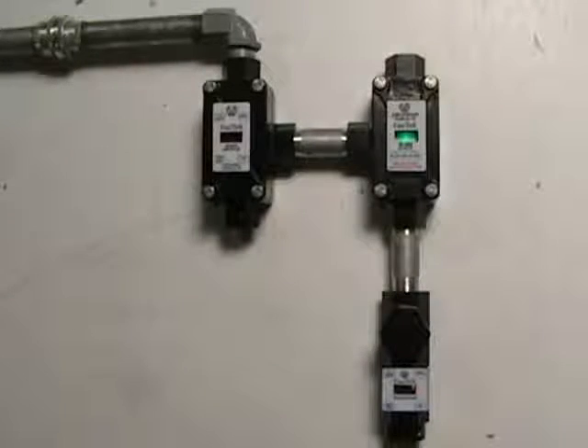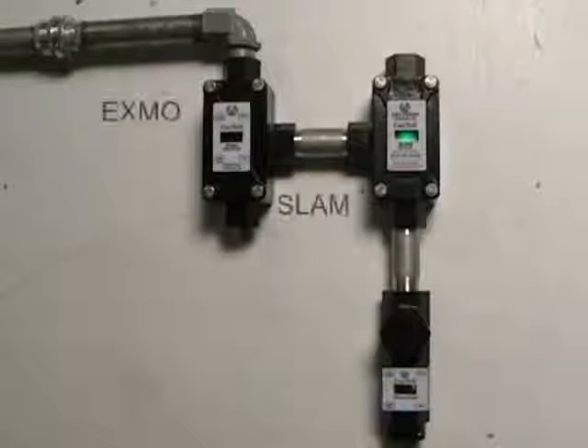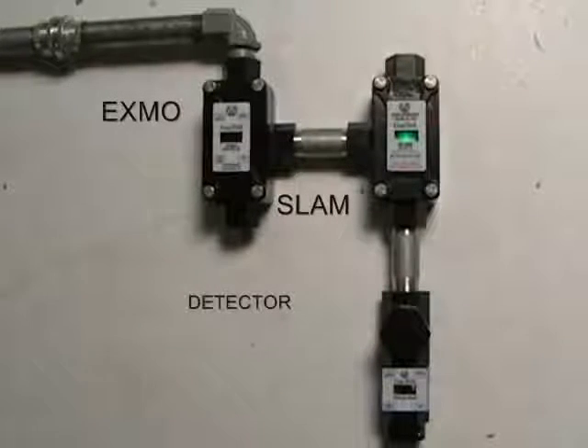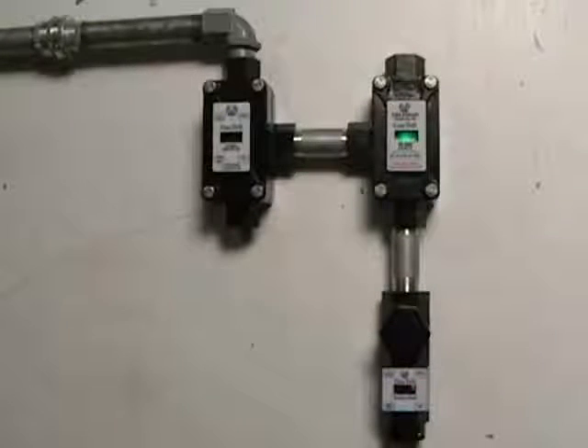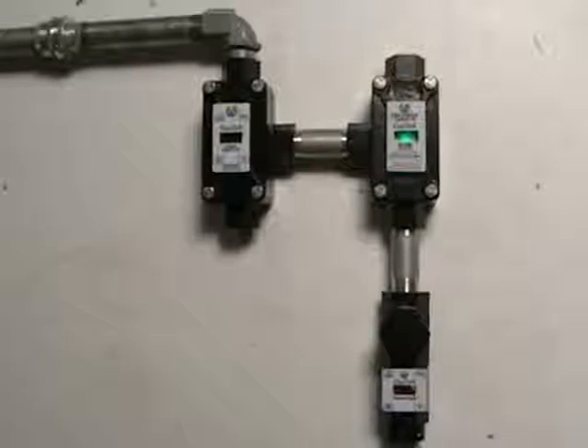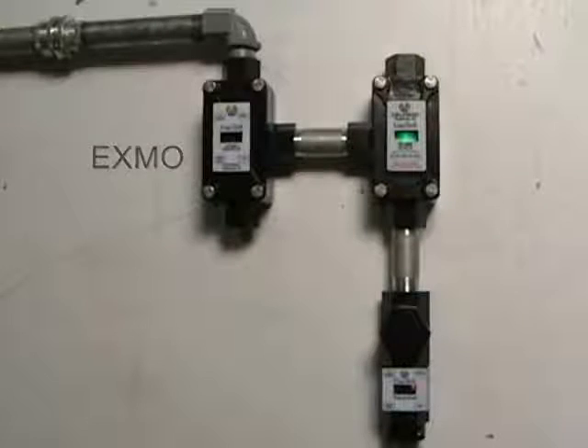Calibration of the GazTell 450 is simple and fast. As shown here, the GazTell 450 infrared detector system is made up of the detector and its peripheral but optional accessory modules. Calibration can be performed through either the detector head or, if that's inaccessible, the extension module, also known as the EXMO.